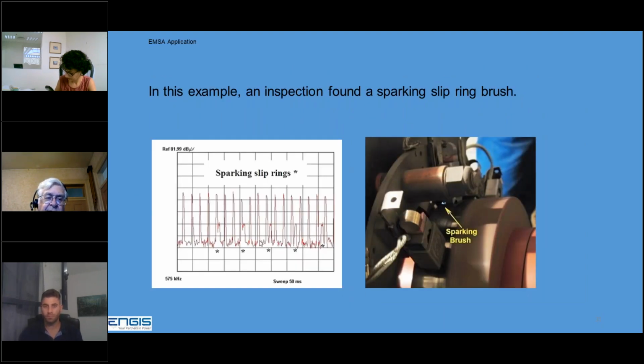Here's another case. All of the diode circuits are good. We have this arcing. It's not at every spike. So that tells you it's a mechanical problem. And again, you could see the sparking on the slip rings in this case. So sometimes the sparking's at the slip ring, sometimes it's in the rectifier itself.